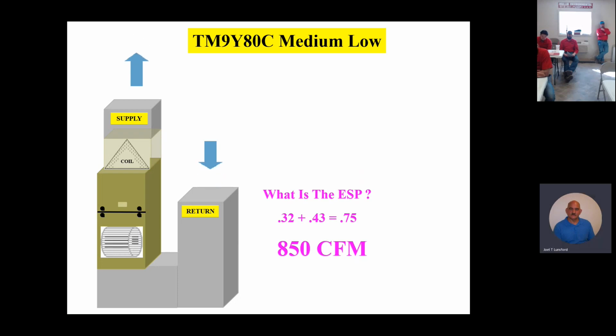So this is exactly opposite. We have most of the static pressure on this job on the return. So where I would start looking at remediation would be to get a bigger return, cut in an extra return, increase the size of the return. You guys get the idea. Another thing to consider is if the homeowner is insisting on using pleated filters, like those little 1-inch pleated filters, you're going to need more return. And so this unit right here might have been okay, but now the homeowner went to the hardware store and bought some of those little cheap 1-inch pleated filters thinking they were doing something, but they're actually killing their equipment. So keep that in mind. Return is really important. And in this case right here, the return path is where we're having our issues.